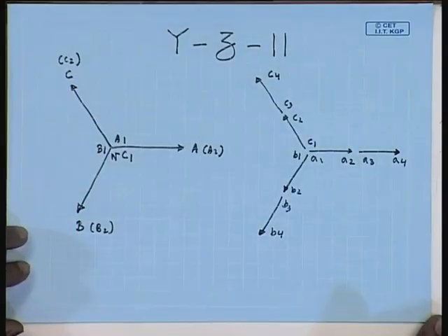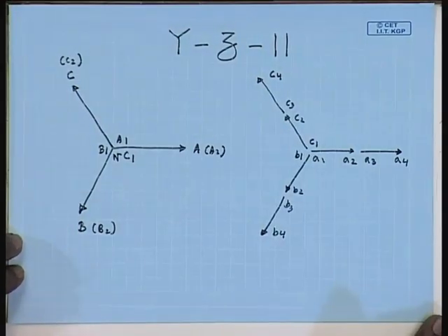In order to have a YZ11 connection, the low voltage side line to neutral voltage should lead the high voltage side line to neutral voltage by 30 degree.